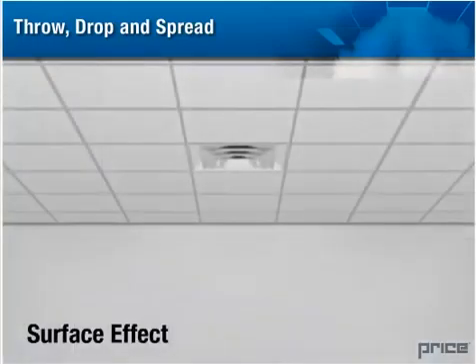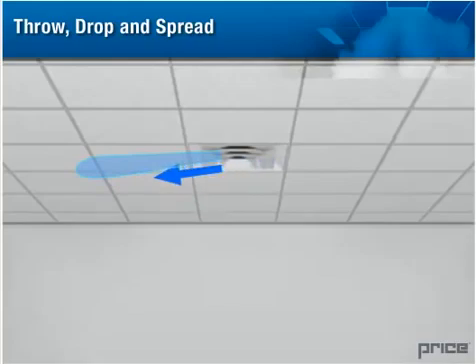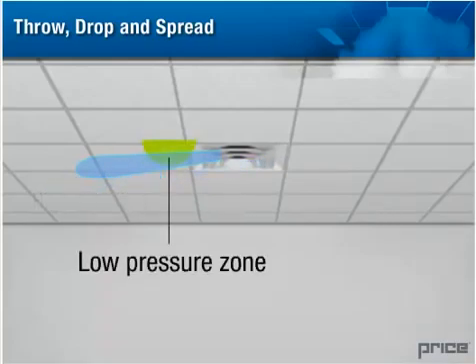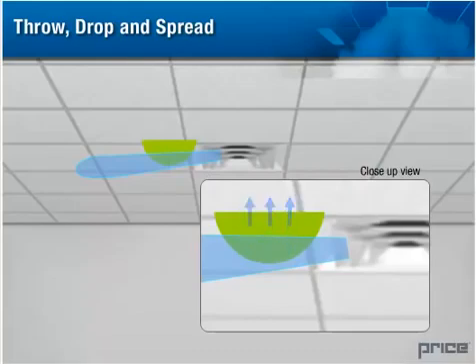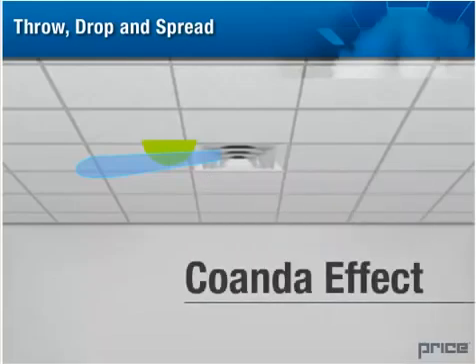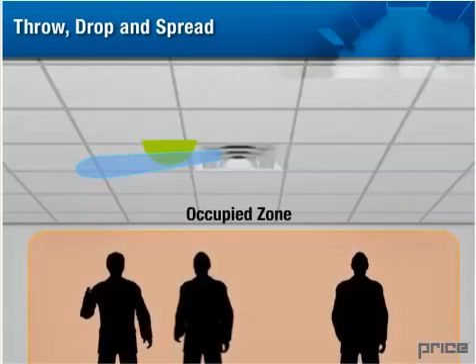When the primary air is discharged from the air outlet at high velocities, it creates a negative or low-pressure zone between the air jet and the ceiling. This low-pressure area causes the moving air mass to cling to and flow close to the ceiling surface, and is called the Coanda effect, or surface effect. This effect has a strong influence on the throw and drop distances of the diffuser.